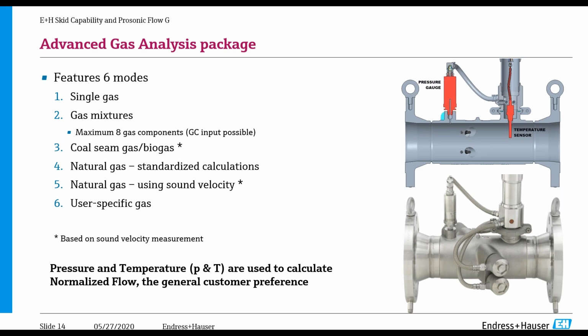Generally there are only 3 components coming up: your gas, water vapor, and CO2, with traces of some other stuff. And what we do is monitor how much methane there is. There's a big difference in sound velocity between methane and CO2. Since we're measuring the time of flight from one transducer to the other, and we do that in the reverse direction too, we take the average of upstream and downstream and get the speed of sound in the gas stream itself. We're able to determine how much methane is in there. So this can give you a good indication of how well the well is working or producing at any one point. It's not a gas analyzer, it's more of an inline process measurement to allow monitoring.